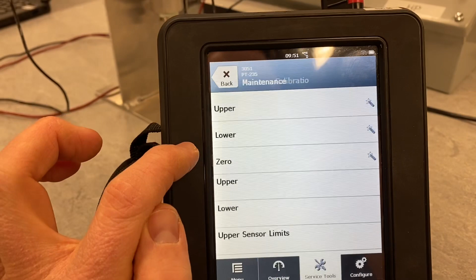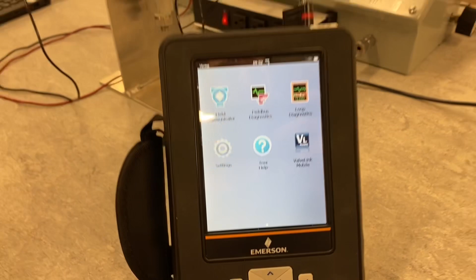It's going to give us a warning that the device shouldn't be used for control right now, so we'll click OK. It is not. Click OK. Apply 0 output to sensor. You can see here we don't have any pressure connected, so it's 0 to atmosphere. Click OK. We return to normal. And there, now we're done. So we can exit back out to our main overview screen. And yes, we want to disconnect from the device, so we click OK. And now what we're going to do is take our AMS Trex device over, connect it to the database, and we're going to see the 0 show up in our audit trail.